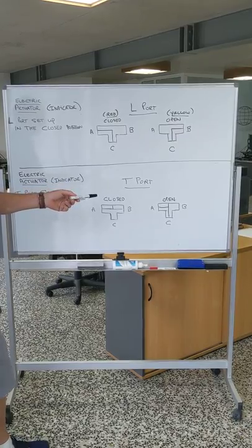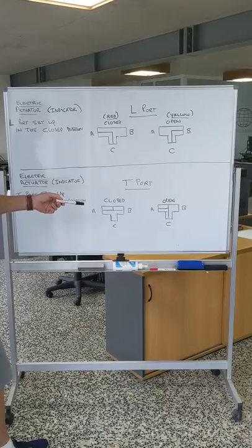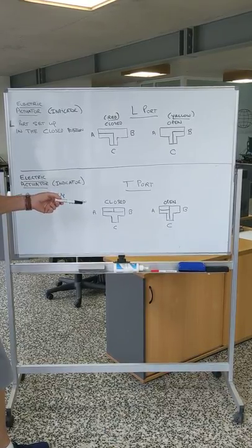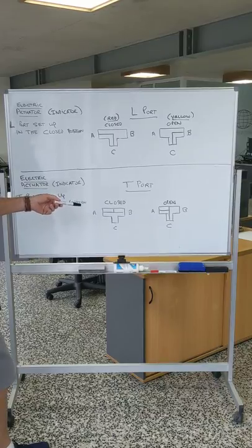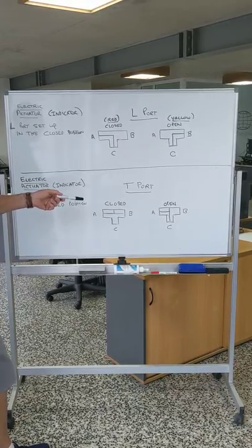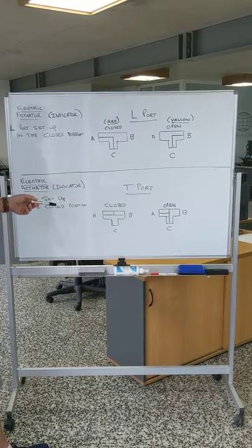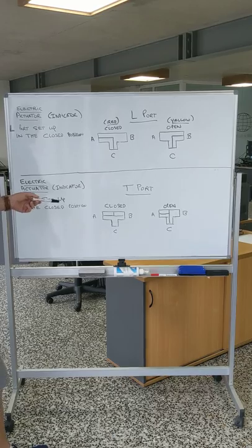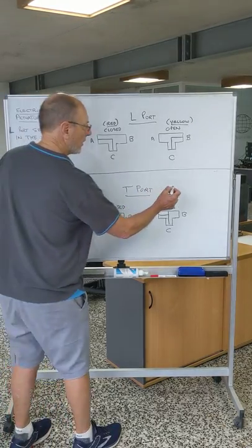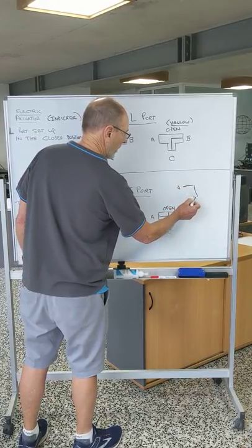For the OM-1 and OM-A, the stops are done with micro-switches internally. If the operator takes the manual override, and if you don't isolate it, operators will fiddle with it. It's probably best to always isolate it. If they do operate it and take it past its 90 degrees, note that actuators always have a rotation of 0 to 90 degrees.